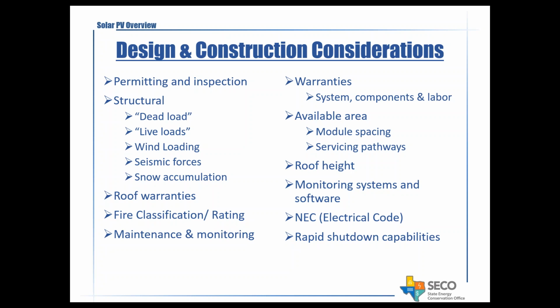Monitoring systems and software are out there. They are available. They're good to have. I like to have them on the front end or where the generation is. It's pretty impressive. You can see what is exactly happening. But we have gone through a lot of places where that system was initially installed, but people changed and so forth. Nobody remembers the password. The manufacturer is no longer there. So the system is there, but they cannot log into it.